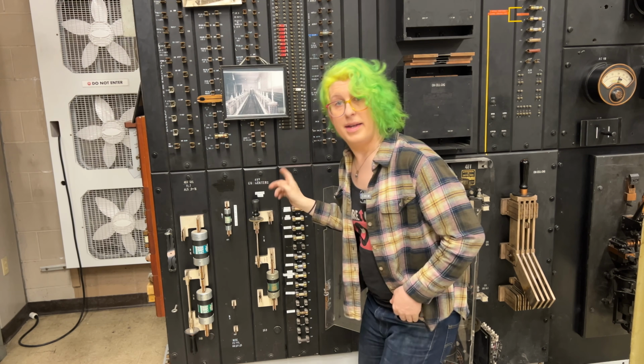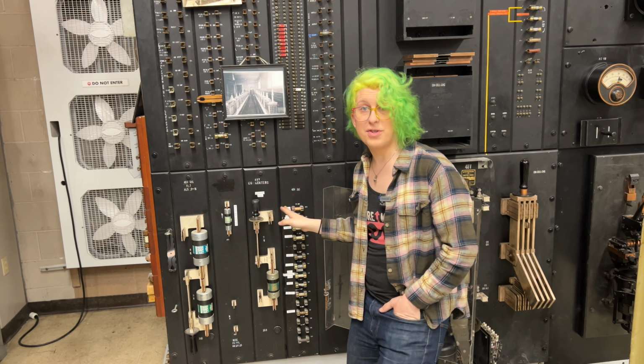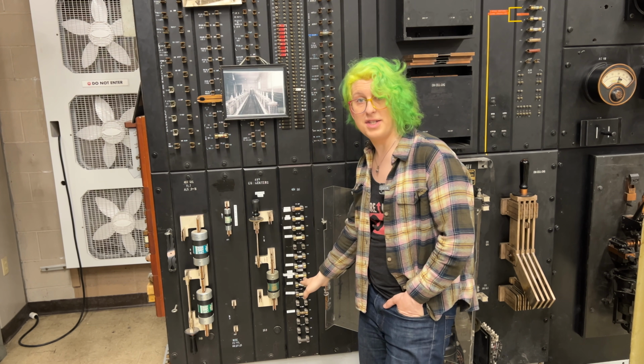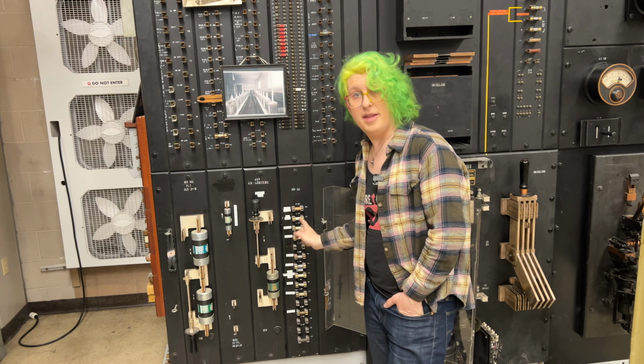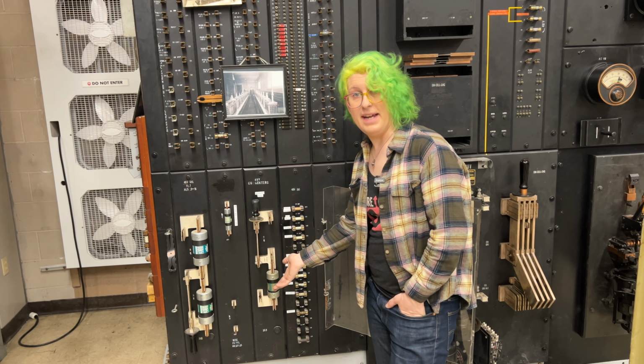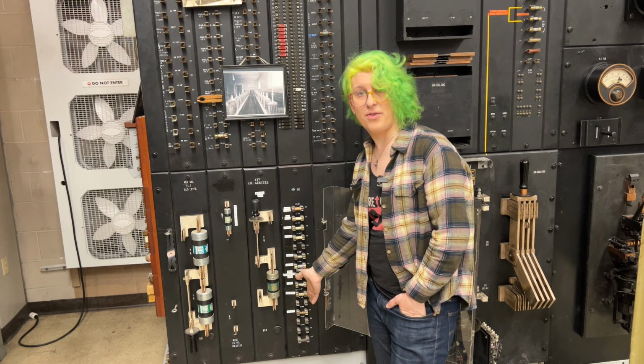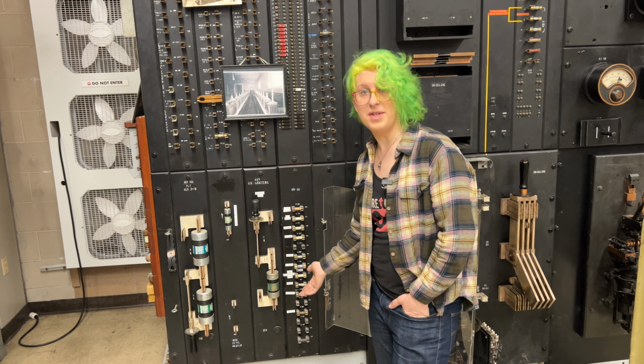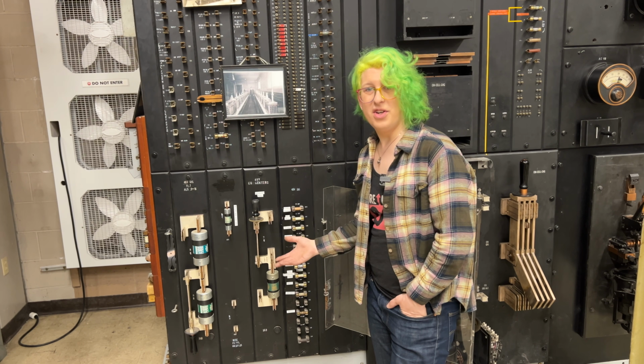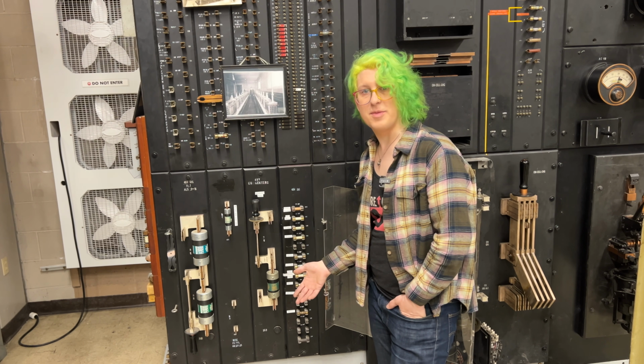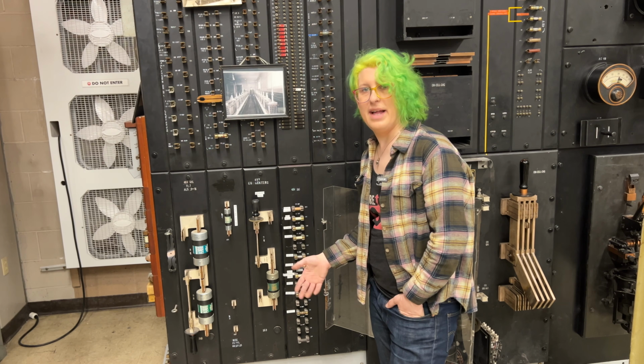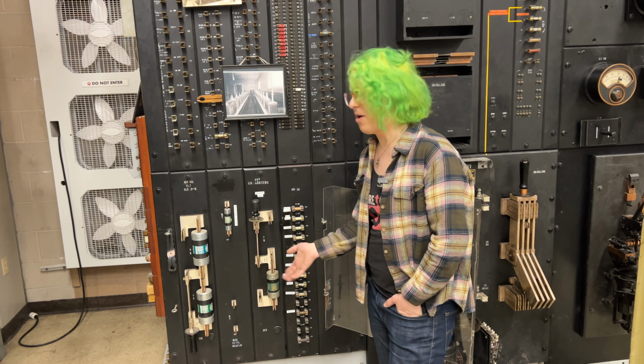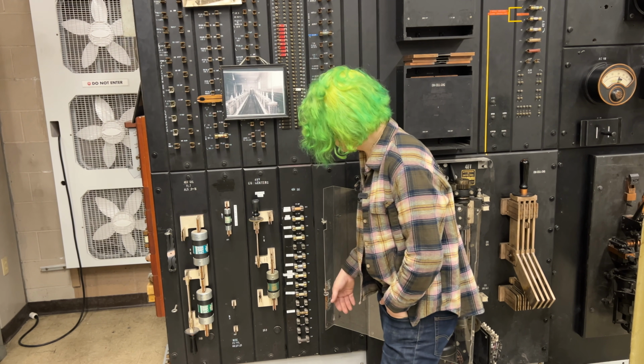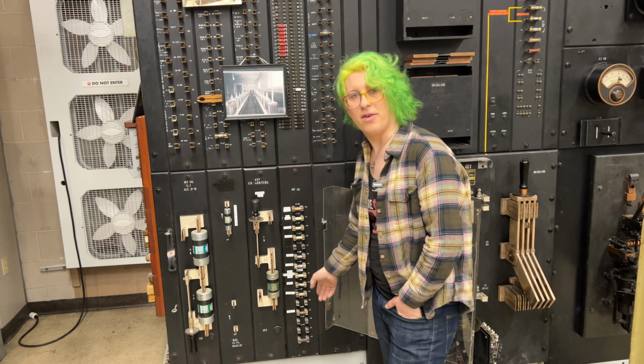Next, we have a bunch of smaller distributing fuses to the other areas of the museum that need them. These fuses are switched by the main knife, so anything connected through here will be powered off when the museum is shut down. This includes some of the other accessories on this power board, the ringing plant, the DC to DC converters for our 24 and 130 volt service, and the big ringing machine over there.